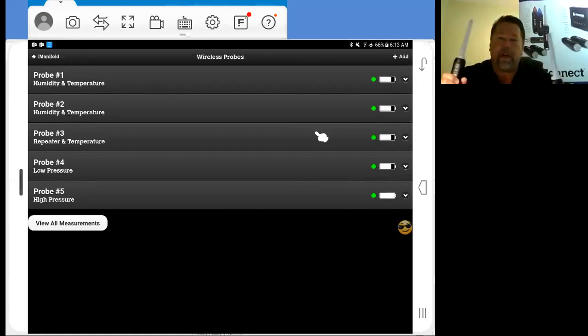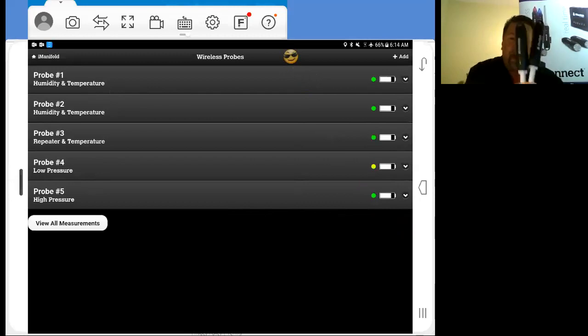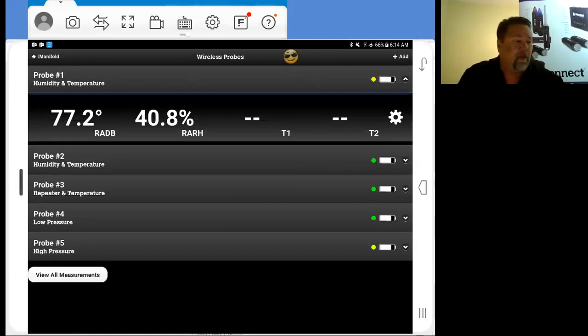But now let's take a look at these. These go into your supply and return. Well, which is which? You can identify them to keep them permanently identified, or it's a simple thing. The system is working. You've got cold air coming out of the supply. You've got warm air coming into the return. If you place the probes whichever way they are, and you need to assign them, right here we've got humidity and temperatures. I'm going to go in here and select probe number 1. Now, mind you, I don't know which one it is on either one of these yet. I select probe number 1, it opens up the probe here. Right now, we've got a return air dry bulb temperature of 77.2 and return air relative humidity.